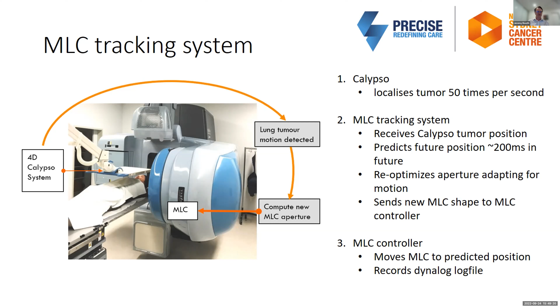We re-optimize the aperture, adapting for motion, and then we send that new MLC shape to the MLC, which then positions itself in the predicted position for the lesion to move into. We also collect dynalogs, which are the log files of the Varian system, to record where the leaves did move, and which also enables us to calculate the radiation dose that was delivered to that particular patient. You can see in this case, it's not a Varian TrueBeam. This is a Varian Clinac, which has a slightly different multi-leaf collimator tracking computer that we interfaced with. So we haven't yet demonstrated this on the TrueBeam platform.